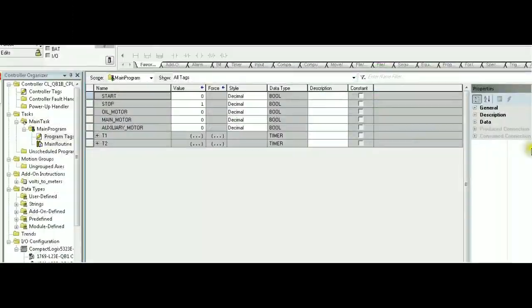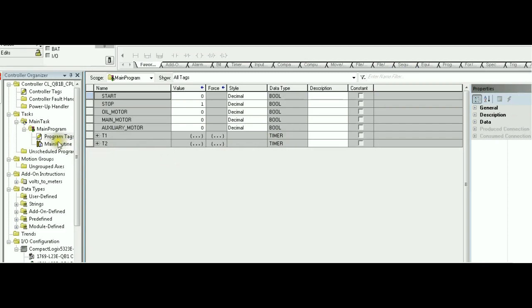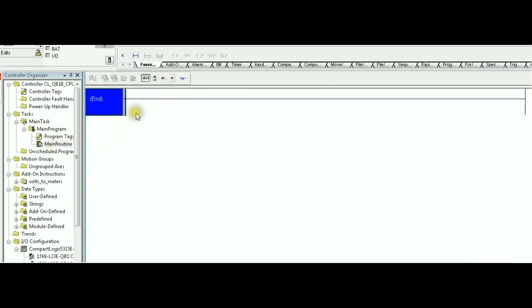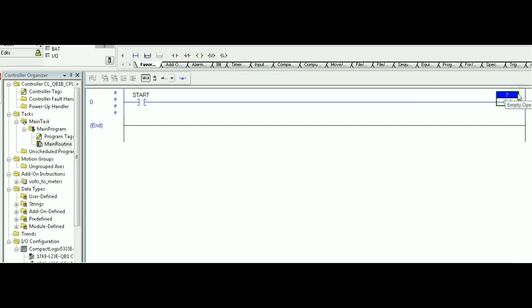The RSLogix implementation, step number one, requires creating the tags. I have already, to save some time, I've created a tag start, stop, and the three motors. As you can see, all of these are booleans. And since we agree that we are going to require two timers to implement the solution, that's T1, T2, and both these have data type timers. Let's go ahead and start the first rung. The first rung, we are going to have an XIC referring to start. And this is going to trigger an OTE for the first motor, which is the oil motor.